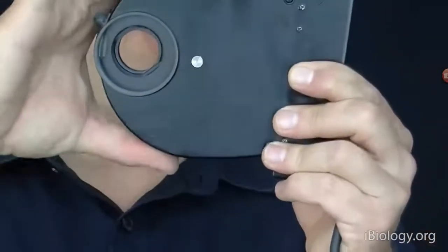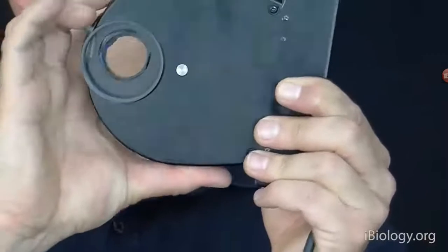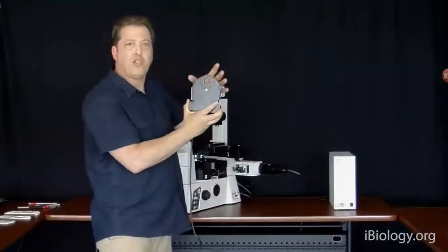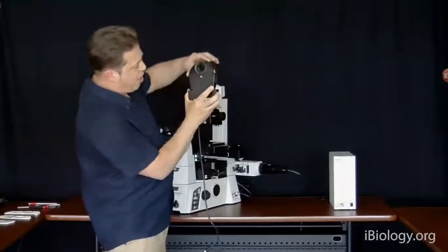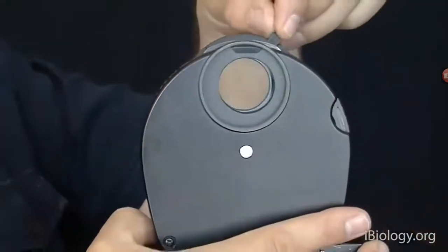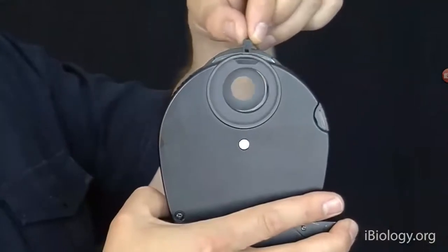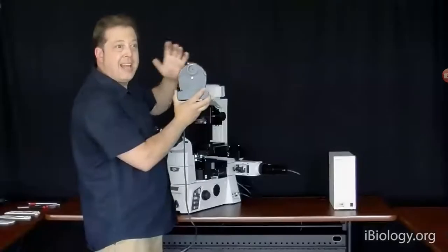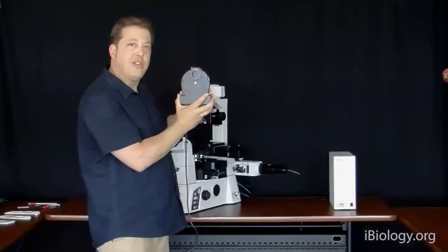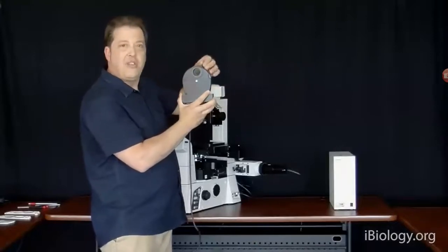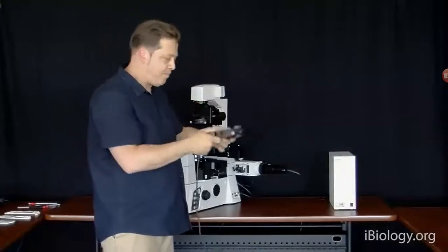Okay. So now that we've removed the condensing lens, you can see in here that there's a number of different spots here, and we have prisms as well as phase rings in this condensing system. And this is where you would hold all of your modules for differential interference contrast or phase contrast. You can also see that there is another iris in here, and this is an aperture iris. This is the first aperture iris in the microscope. And that's going to actually adjust the cone of illumination and trade off contrast for resolution in transmitted light techniques.